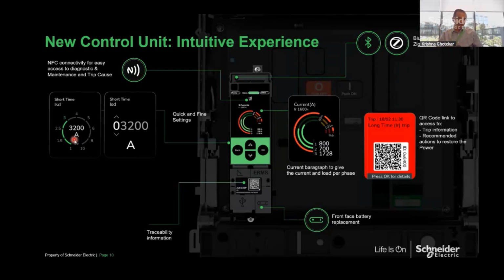So thanks to the digitization, what we are bringing. As a first step, yes, you can set it, let's say to 3 times the rated current, which is 3200, and then we have an option to do a fine tuning. Now this fine tuning can be done within 1 ampere. So I can set it to 3199 or 3198. So whichever rating you want, it can be exactly set to that particular rating as per the recommendation from the consultant or whoever is doing the design or the selectivity study for the entire installation.